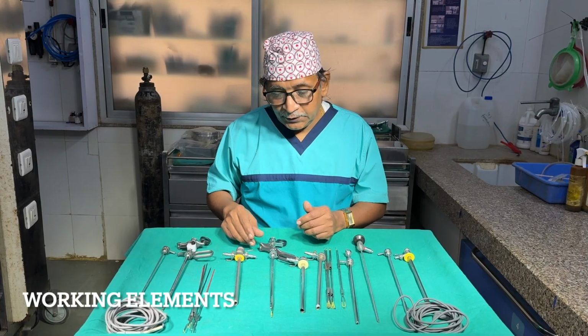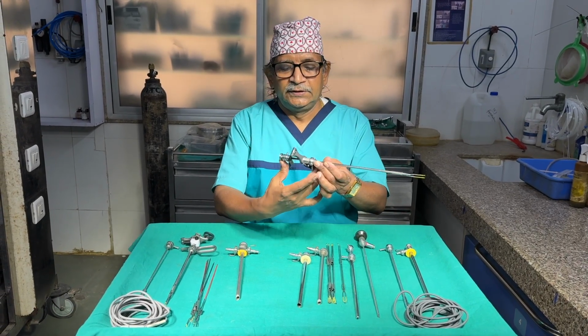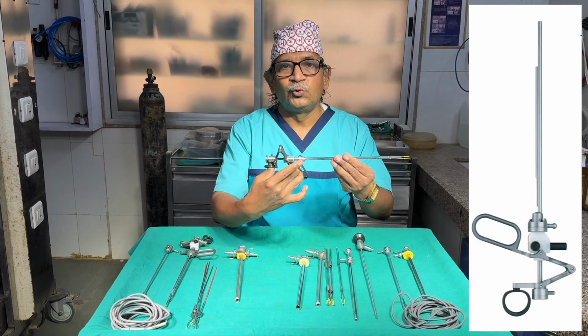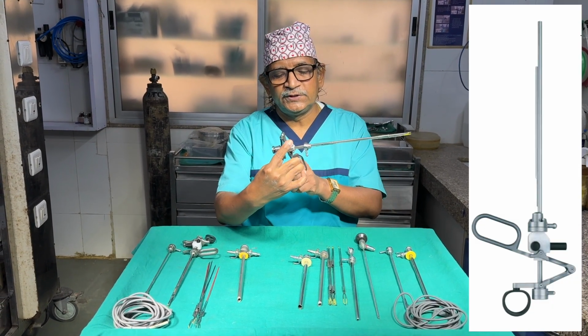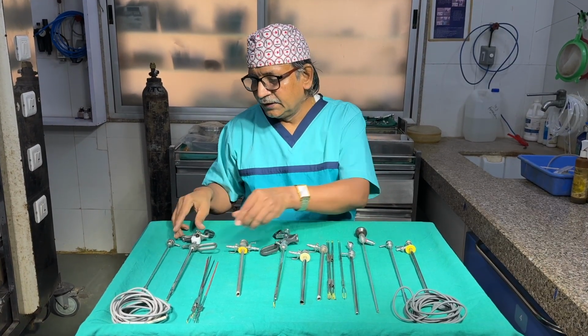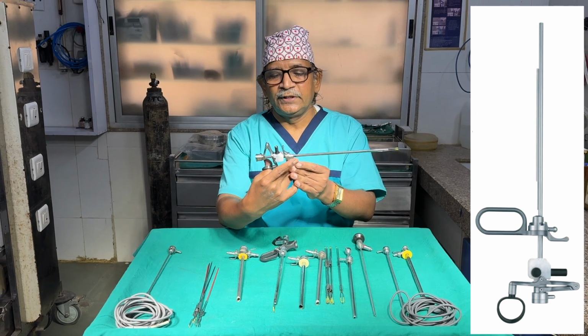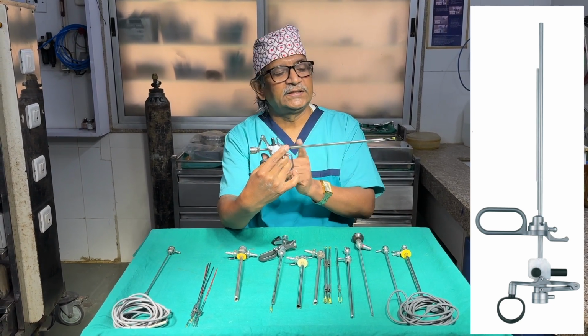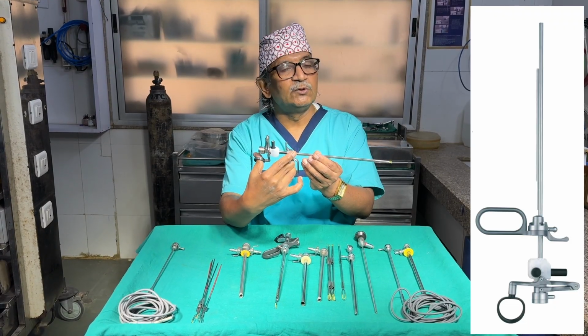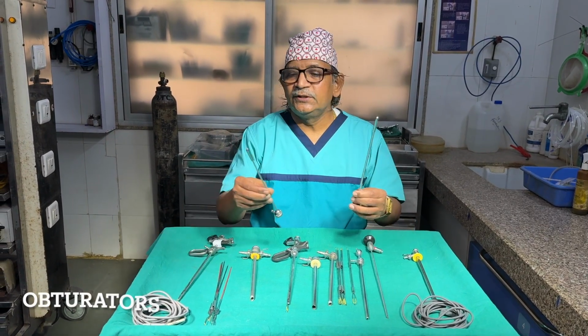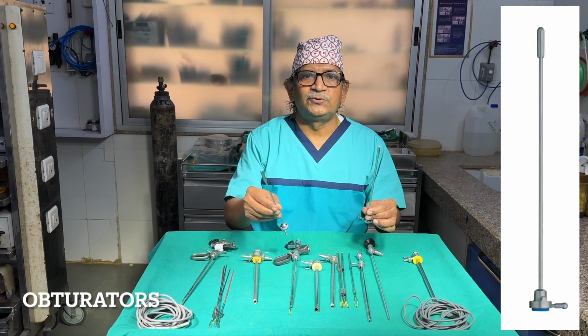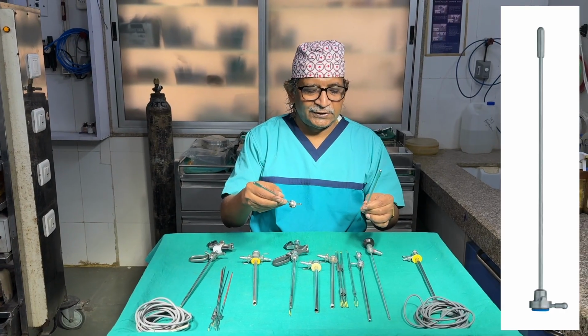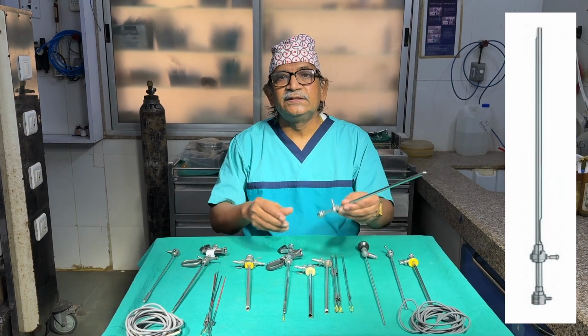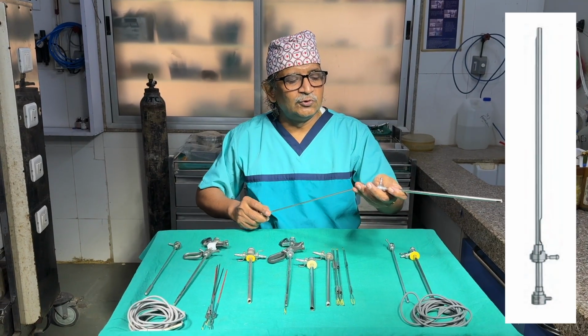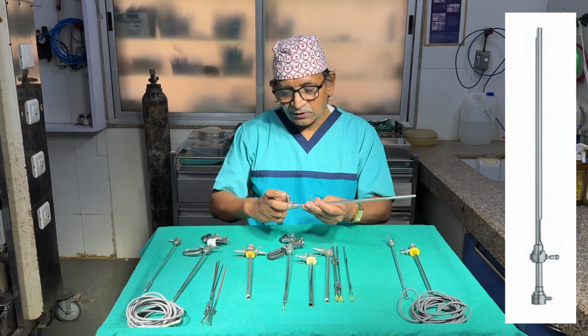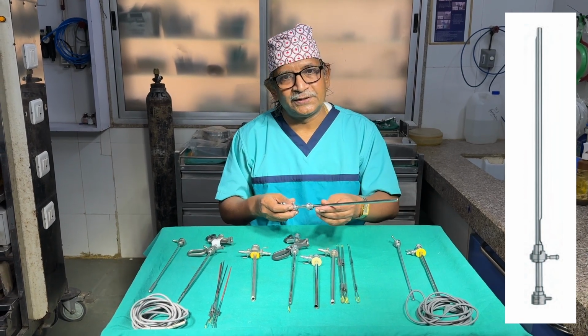The working elements for the TURP also come in two different forms. This is the active, also known as the Baumrucker system, where the movement of the loop is by your fingers, and this is the passive, where the recoil of the loop is by the spring. With the thumb action, the loop is going out, and when you retract the thumb, the loop is coming in. This is also known as the Nesbitt system. So these are the obturators which are known as standard obturators. These are not visual obturators. You have to pass the instrument in the urethra by tactile feedback, whereas this is the visual obturator. You can put in your telescope through the visual obturator, and you can observe the passage of the instrument through the urethra with the help of the visual obturator.